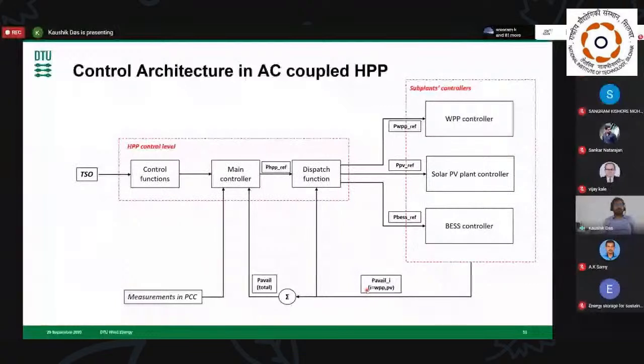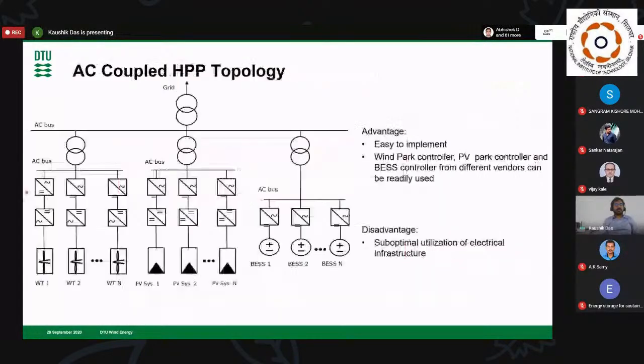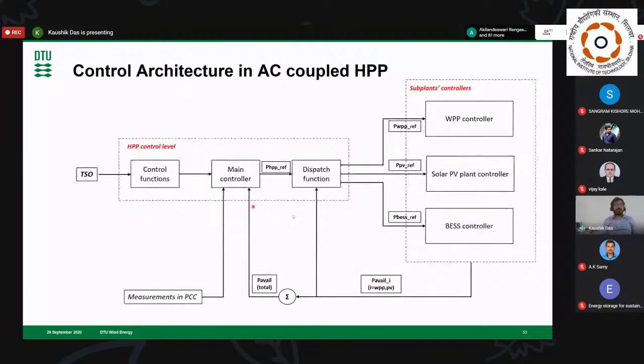This is a typical control hierarchy for any hybrid power plant: you have the wind power plant controller, solar PV plant controller, and BESS controller, connected to the individual turbines. For example, this will dispatch set points to individual turbines. The solar PV plant controller sends set points to individual strings, each with an inverter, and sends a set point to each inverter. Same for the BESS plant.